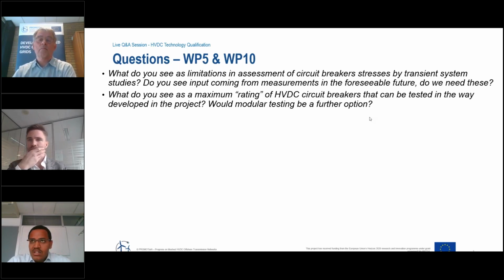But as we saw for 320 kV, every breaker had around 500 kV TIV coming from the breaker, which stresses the system components. So there are different components in this test method, like transformers, circuit breakers, spark gaps, and some reactors. All those components must be able to handle this stress which is coming from the breaker. So those are the limitations.